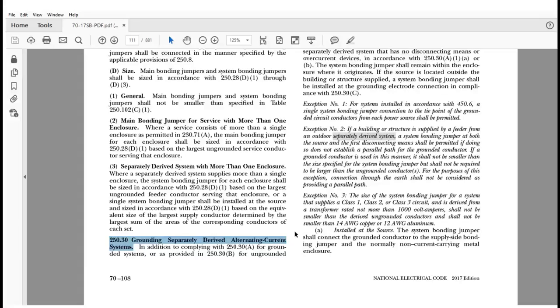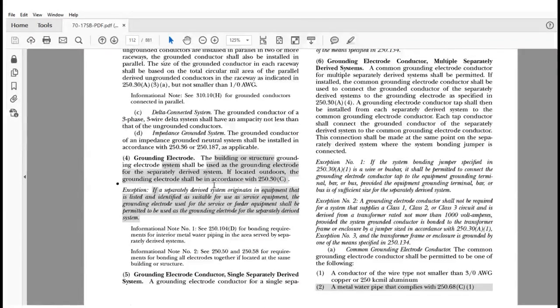Language was in there. Well, for the 2017 edition, I will scroll down to the changes here. You'll notice the changes here in gray text. In the 2017, any of the building or structure grounding electrodes that are present can now be used. It doesn't have to meet the 1 and 2 as previously, when it said you have to go to the water pipe or the structural steel, whichever is nearer to you. And then if these two were not available, then you could use the others allowed within the code. All right? But you had to use these two first.